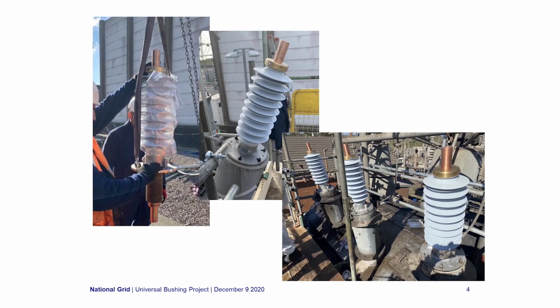All 6 of those bushings have already been put to good use on transformers at 2 of our substations. The kits were delivered to site and the adapters selected appropriate for the needs. The bushings and adapters were assembled easily on site with push-fit and lock connections, and the installations were made easier by the new bushings being lighter than those they were replacing. All 3 new bushings were installed in around 90 minutes, which was less than we expected, especially for the first job. Once the job was complete, the rest of the kit was sent back to stores so that the used components could be replaced.